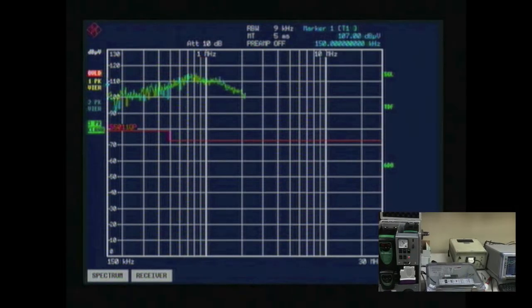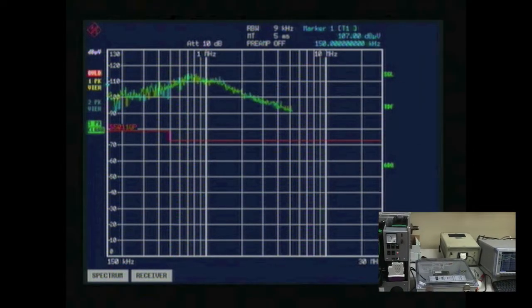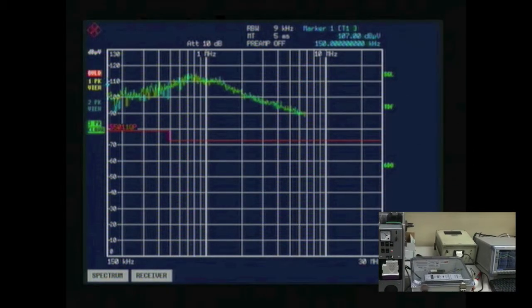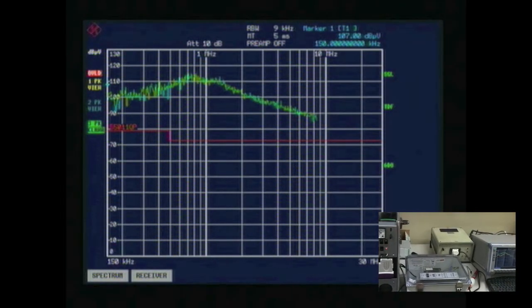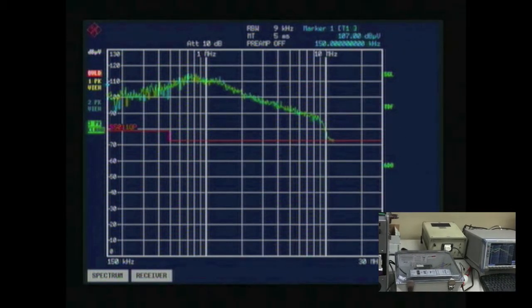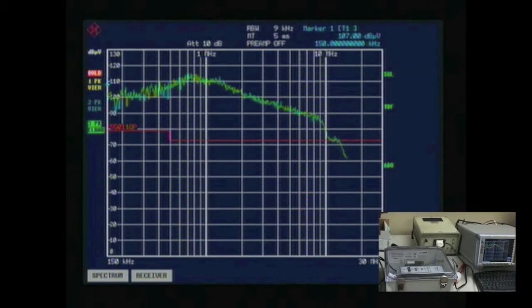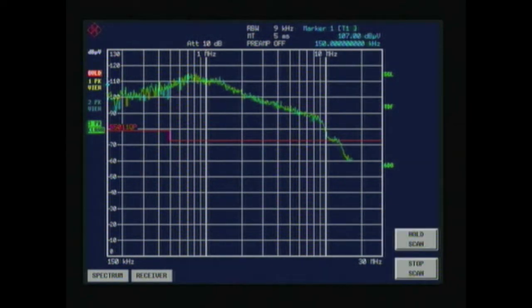This graph line in green measures the electrical noise generated by the AC drive without either a line reactor or EMI filter connected to the drive. The red line on the graph is the European Standard and FCC Part 15 limit.